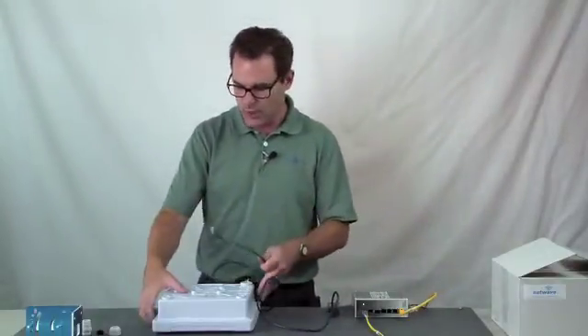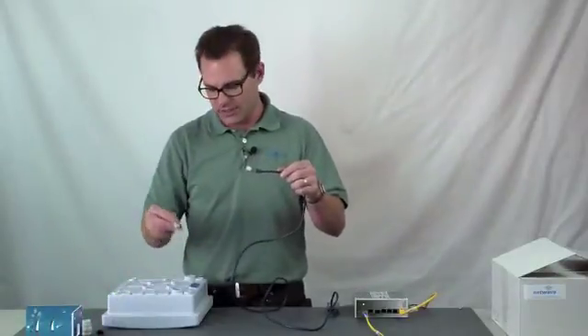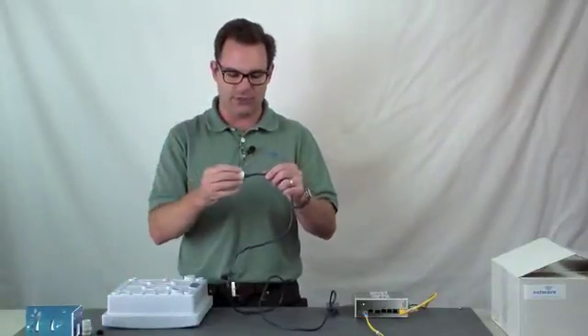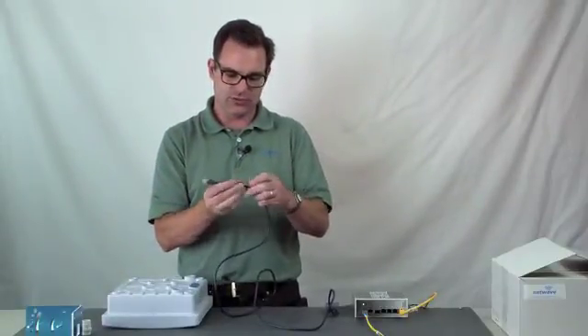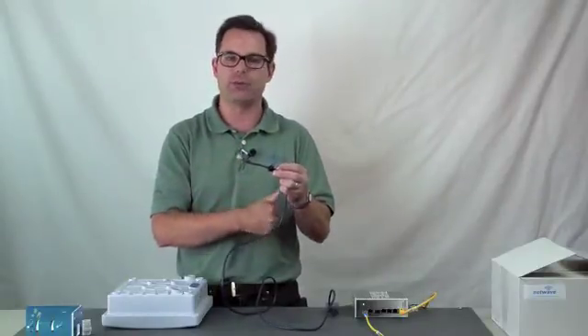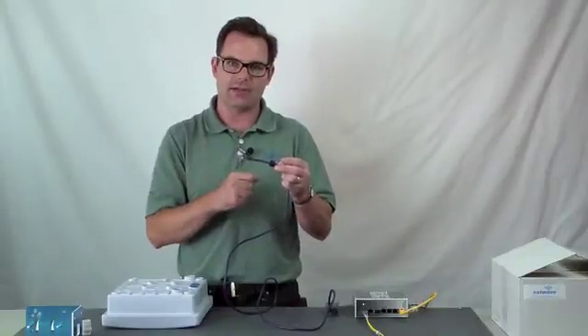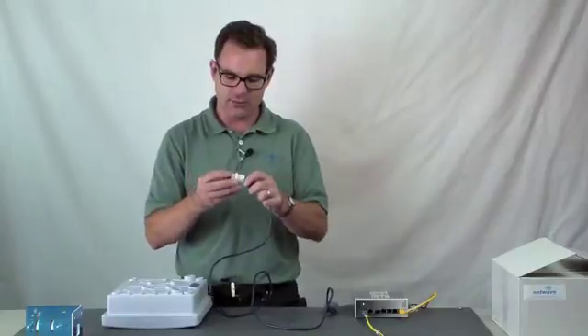And then, we will start to put together our gland. You're going to work backwards in terms of how you're going to put it together. Your final cap is going to go on first, then the rubber gasket. You'll note that this is a pre-terminated cable, which is a great feature. That means you don't have to put through an unconnectorized cable and then add the connector after you put all this material on. This will definitely save you some time during installation.